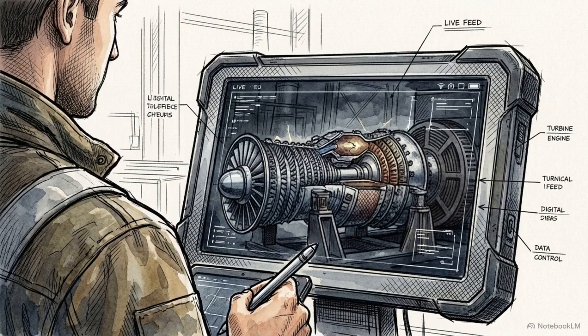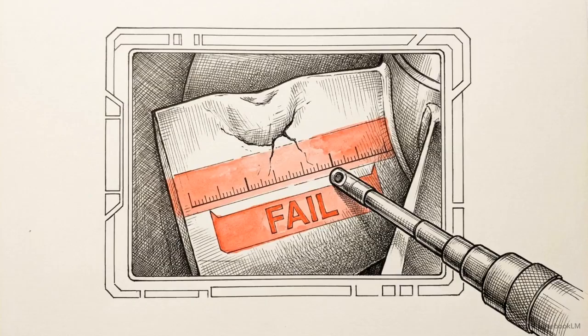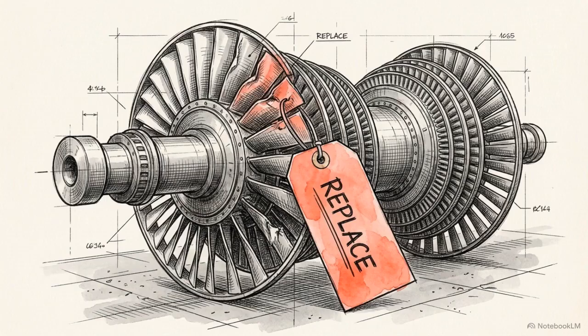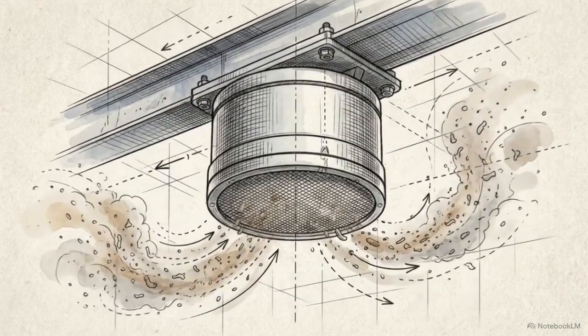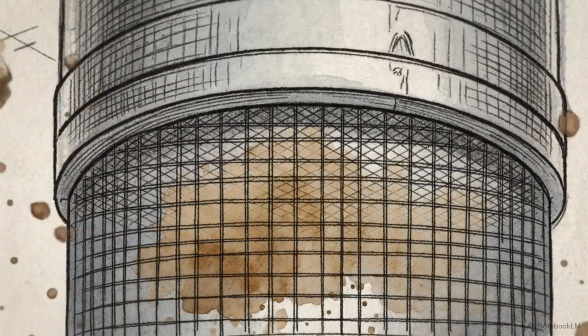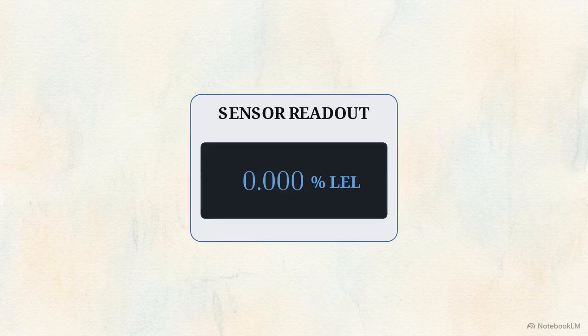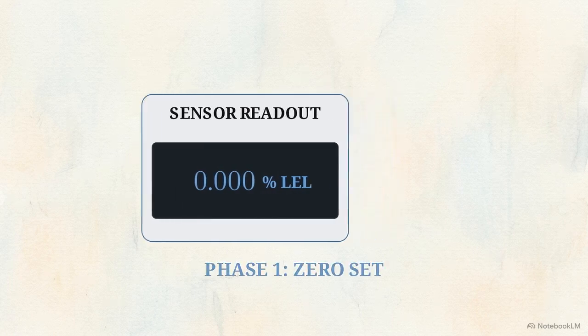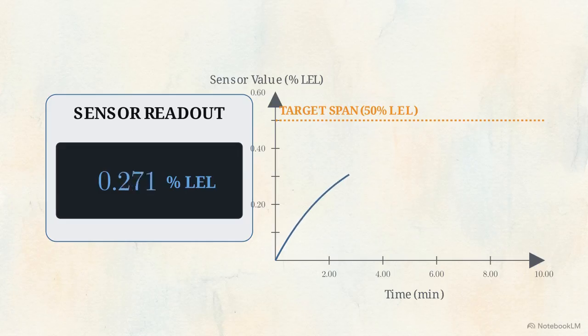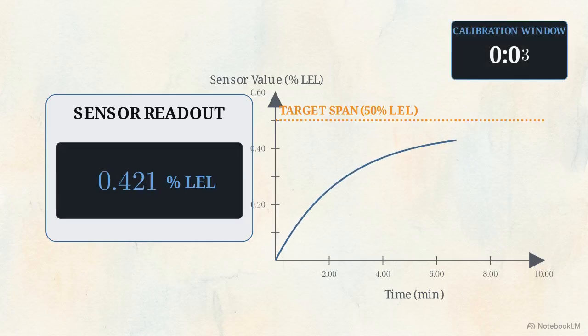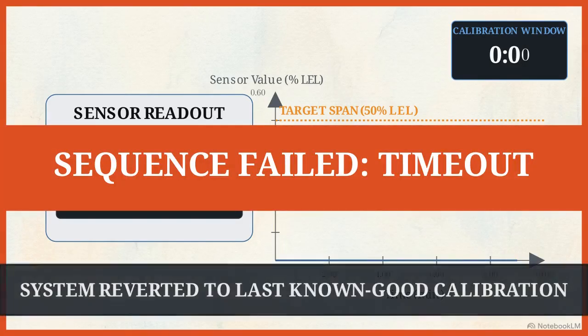Technicians gather mechanical evidence using borescope cameras to inspect the hot section without teardown. Every crack or dent found on a blade is measured against a specific tolerance bar. If the defect size exceeds the limit, the component is flagged for immediate modular replacement. Environmental monitoring is equally rigorous. Combustible gas sensors protect the enclosure from invisible leaks, but they drift over time as filters accumulate dust. Calibration requires a strict sequence, confirming a 0 reading in clean air, then applying a known test gas to set the span. If this process takes longer than 12 minutes, the system aborts and reverts to its previous calibration to prevent a life safety monitor from being left in an unverified state.